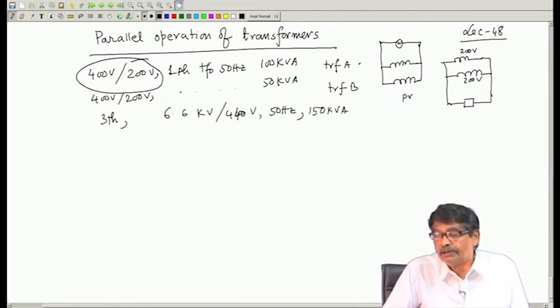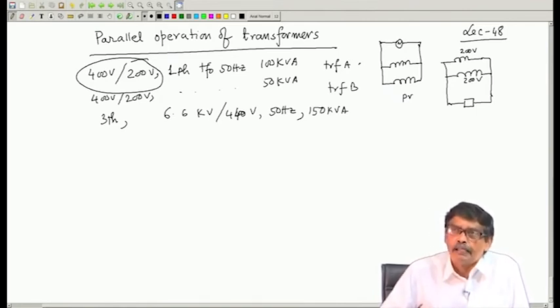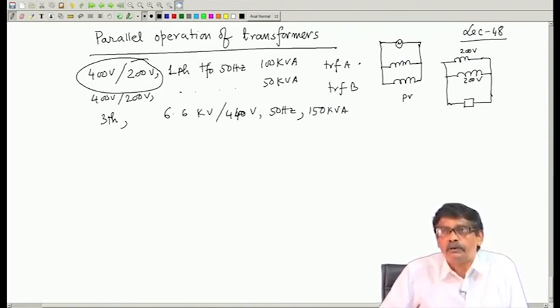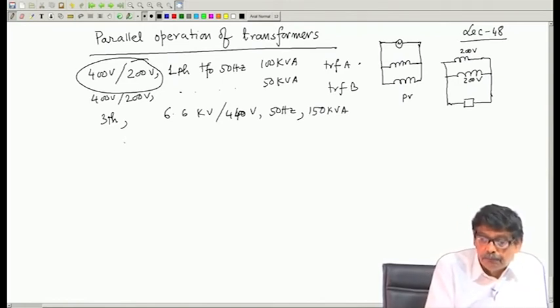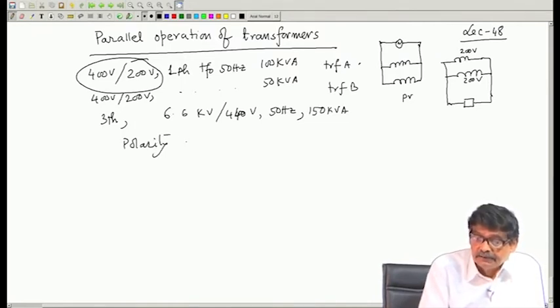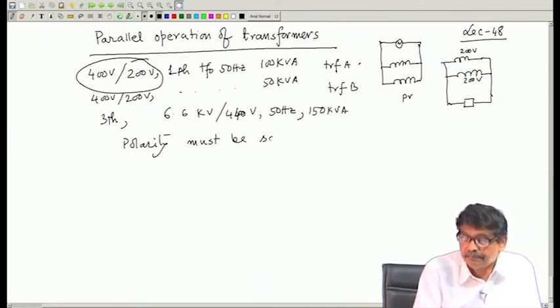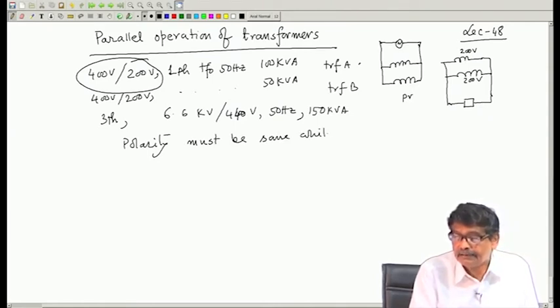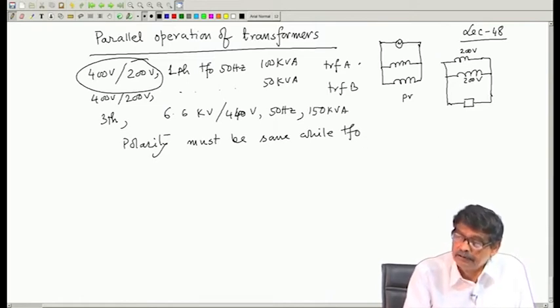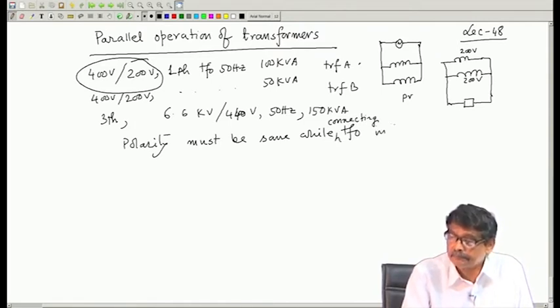Then the third important point, which is a rather practical problem. After you have got these two transformers which you want to operate in parallel, you must ensure, that is very important, that the polarity test, the polarity must be the same while connecting transformers in parallel, otherwise you cannot do it.